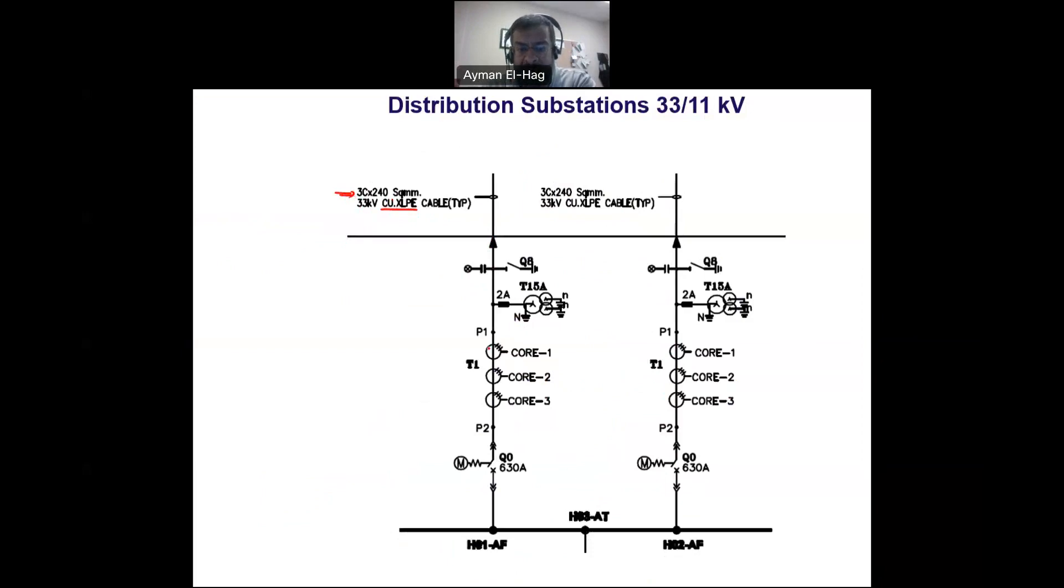Here we have core 1, 2, 3. These are actually current transformers. We have three current transformers in each phase to measure the current at the high voltage side. We also have a PT or potential transformer to measure the voltage at the high voltage side. It's very important to measure the currents and voltages at both the 33 kilovolt and the 11 kilovolt busbars.